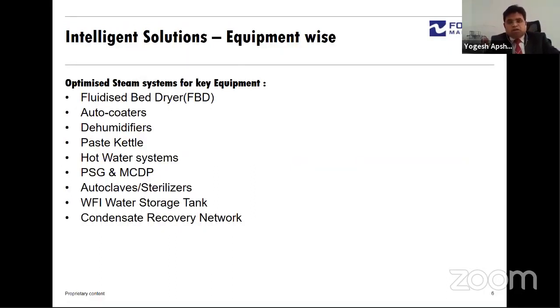So what are the intelligent solutions we have come up with, equipment wise? With our extensive study, we have identified the main steam users in the formulation plants: fluidized bed dryers, autocoaters, dehumidifiers, paste kettles, hot water systems, pure steam generators and WFI stills, autoclaves, sterilizers, bung washers, the WFI and purified water storage tanks, and the condensate recovery networks. These are the typical steam hookups, or steam users. The majority of the steam in formulation plants is used in these applications.